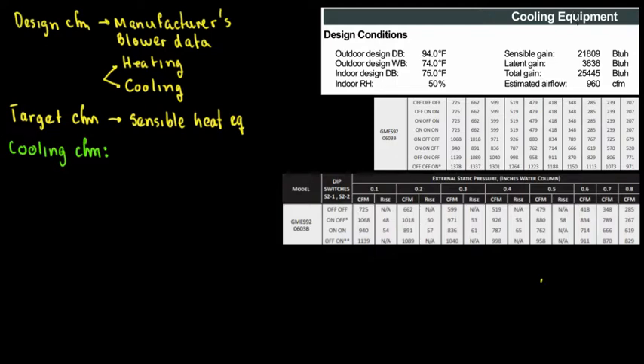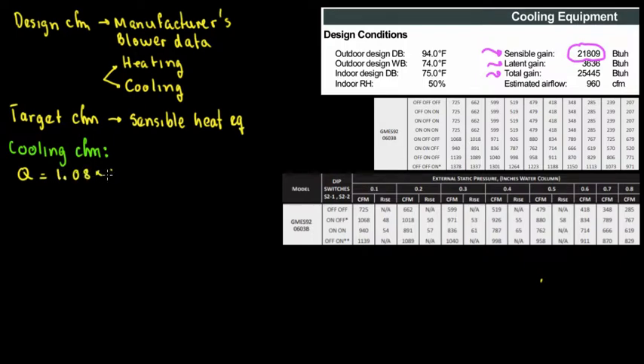So for cooling, we have sensible, latent, and total heat values. The cooling CFM is determined by the sensible heat equation: Q equals 1.08 times CFM times delta T.